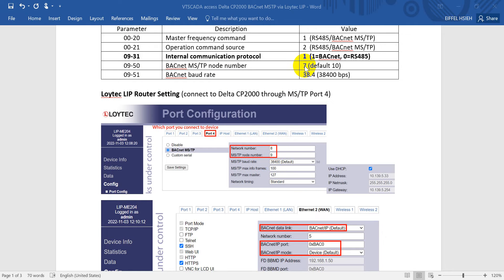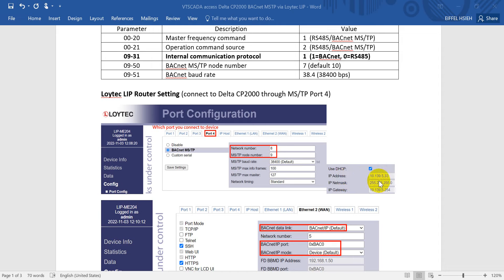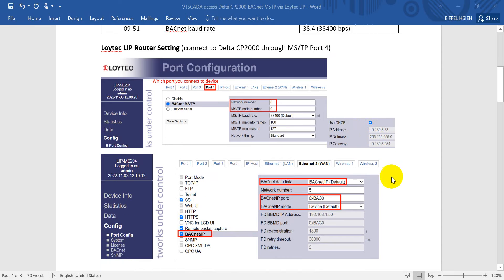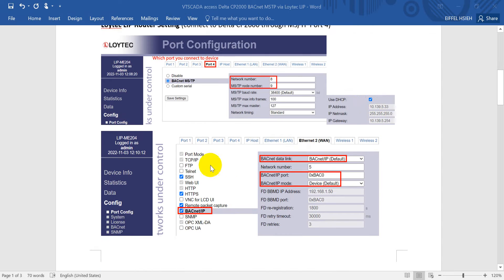For the MSTP, CP2000 is 7 and the router is 9. We keep the same port rate. This is the IP address for the BACnet router: 10.139.5.33.